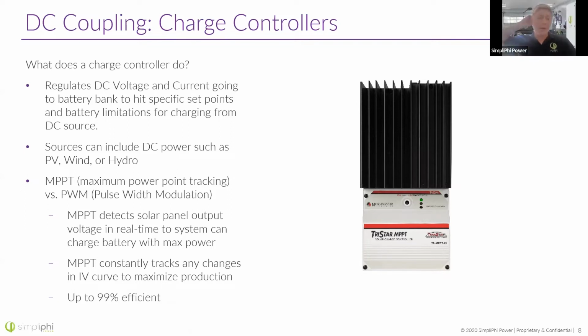All right, so MPPT stands for maximum power point tracking. Maximum power point tracking is going to see the solar panel voltage at all times. And it's then going to say, okay, right now I'm sitting at 100 volts. If I increase the array voltage to 100.2, are we producing any extra power? No? Okay, how about 99.8? Any extra power there? No? Okay, back to 100.